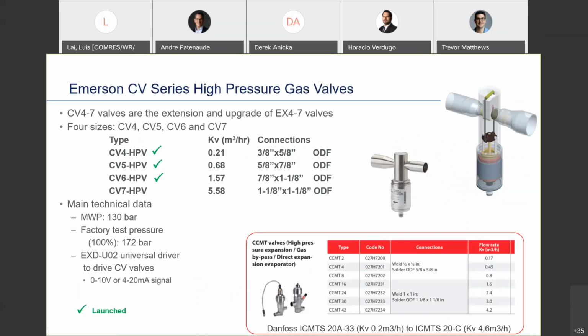Sporlan's developed a valve. So many OEMs have developed valves through the years. Most popular has been the ICMTS and now the new CCMT valve. The 4, 5, and 6 valves that are currently launched with a Kv factor of 1.57 gives us capacity equivalent to Danfoss all the way up from the 2 all the way to the 16. The larger version, CV7, that has not launched yet, would cover the remaining 3 Danfoss capacities.